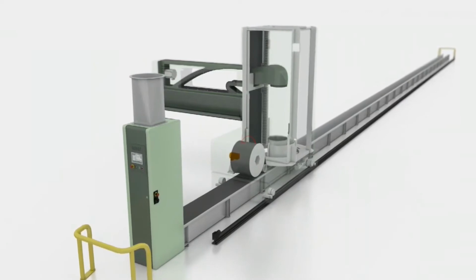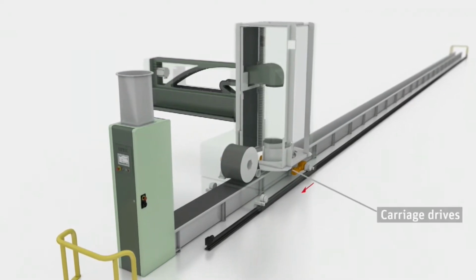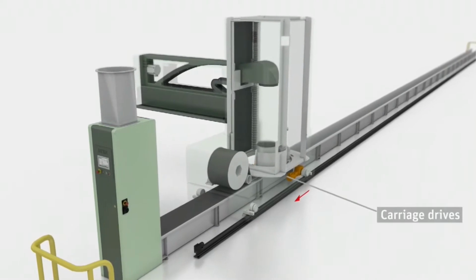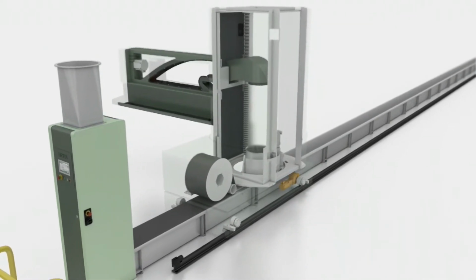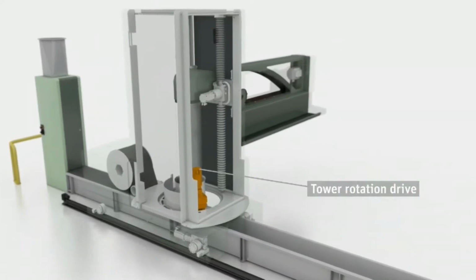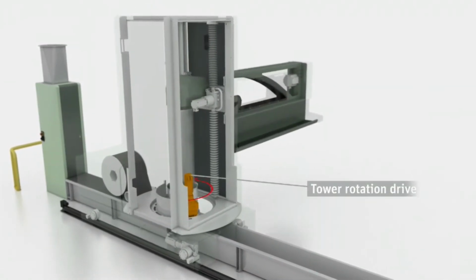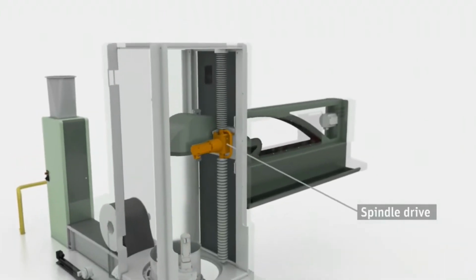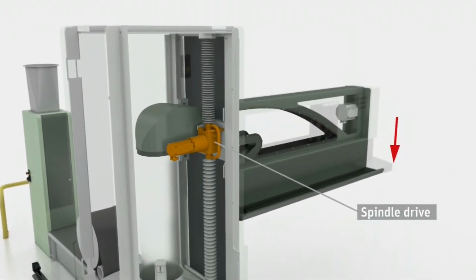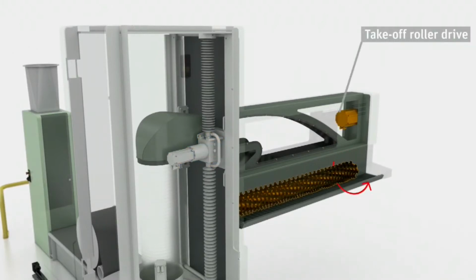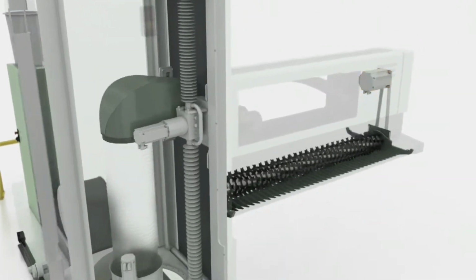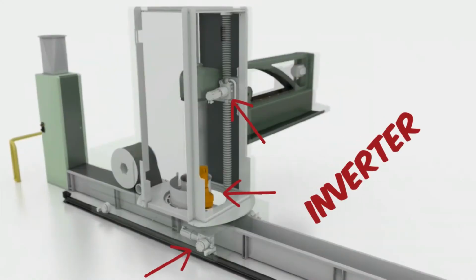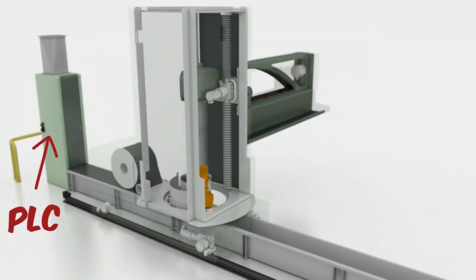There are some motors inside this machine. One is to move the bale opener from first to last beside the bale row. The other one is to rotate the bale head, and one is to move the bale head up and down so that it becomes closer to the cotton bale. Another one is to run the roller tooth, and there is an inverter to control the motors, and the motors run with the signal of the PLC. The PLC gives this control signal to the inverter.